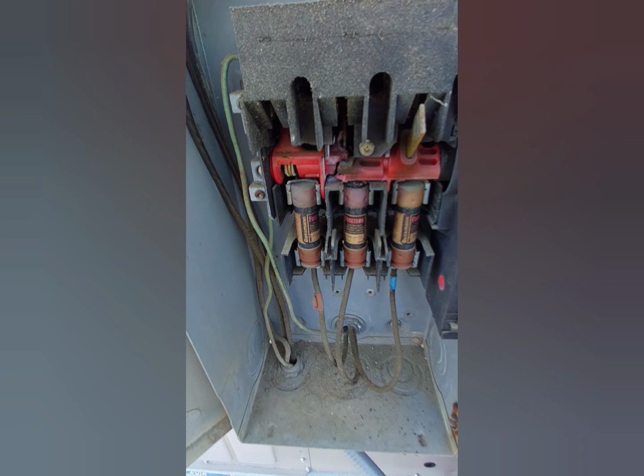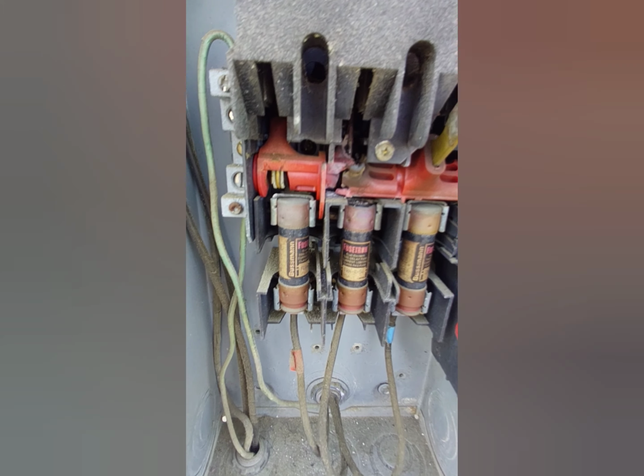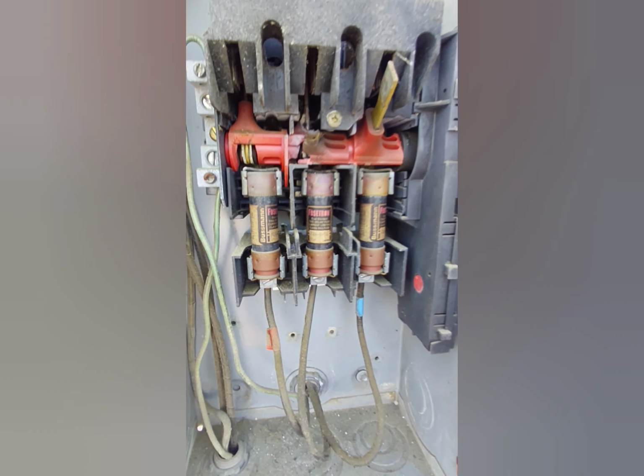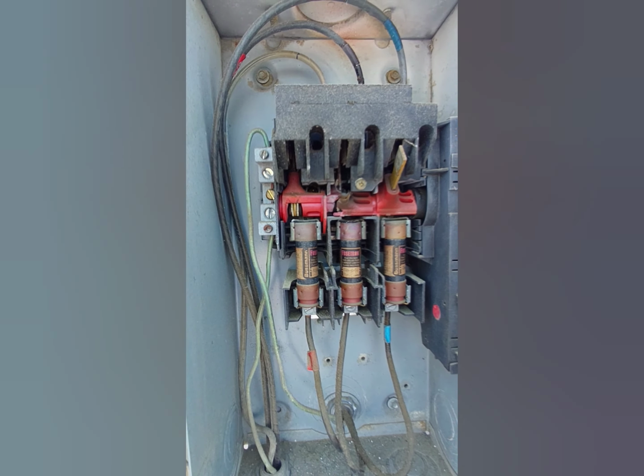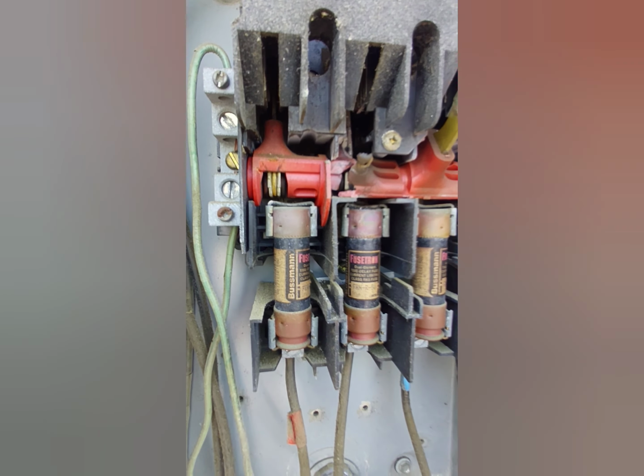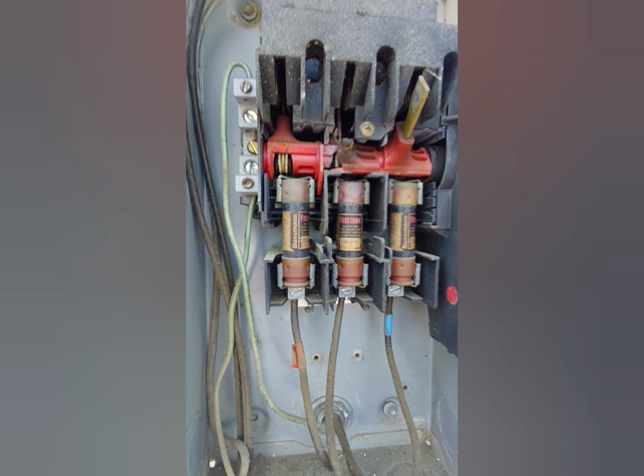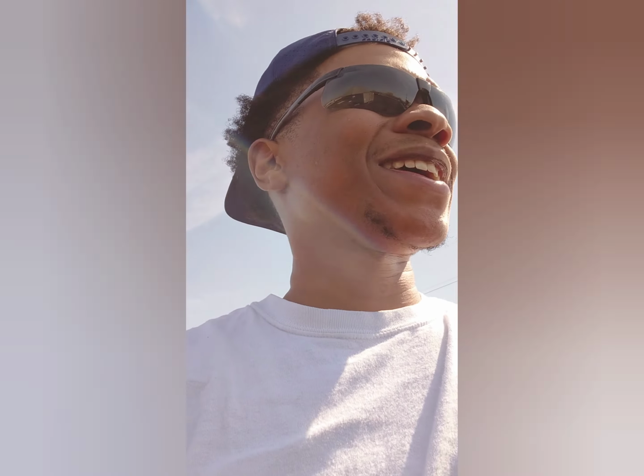Okay, this is not good. So yeah, they need a disconnect, and you can smell the burnt smell. So yeah, this disconnect's got to get replaced. I can't do nothing until I replace this. So one, I gotta call and get approval to see if I can replace this. I'm pretty sure they're gonna let me replace it. We're gonna replace that, then we can come back and see where we at. Pretty simple.